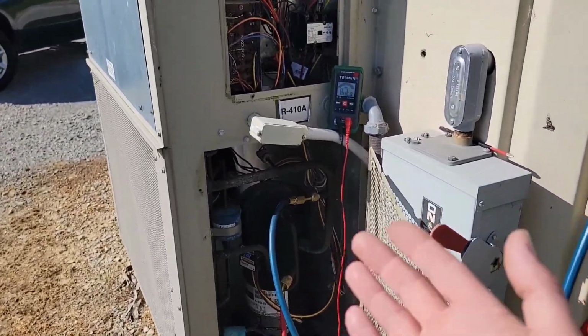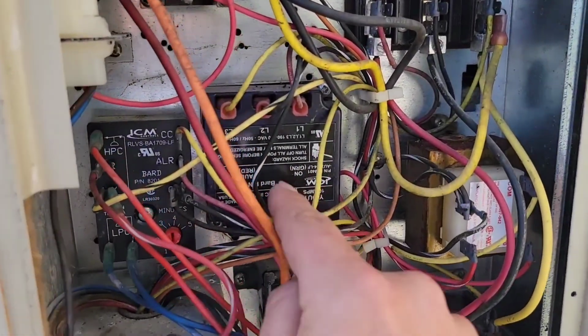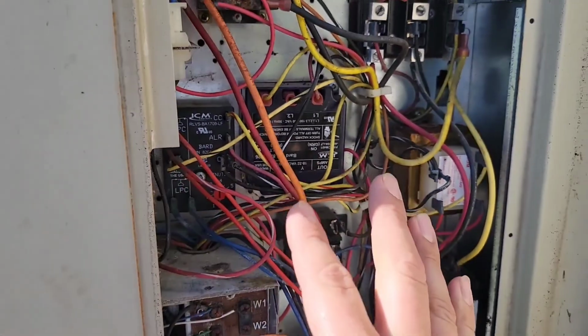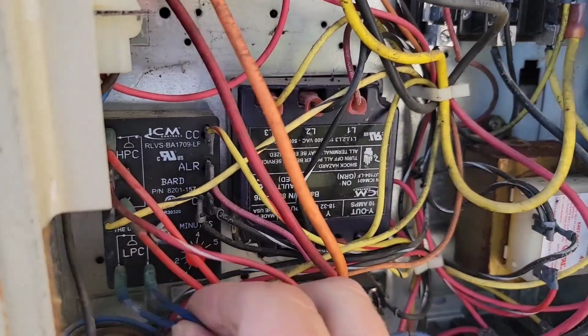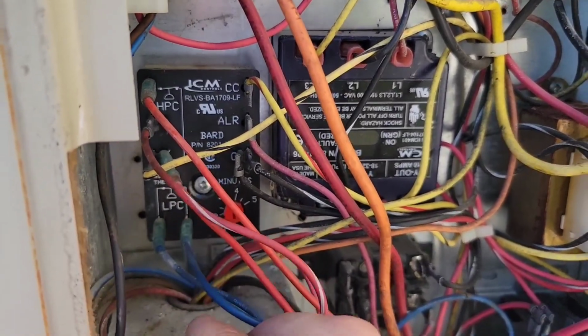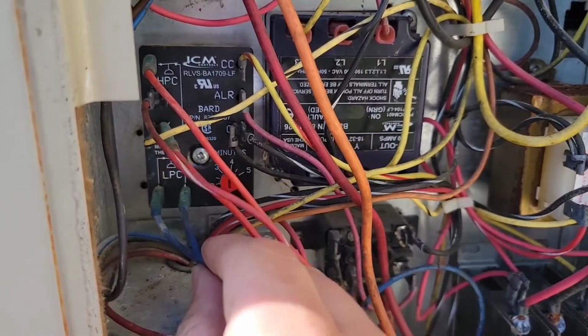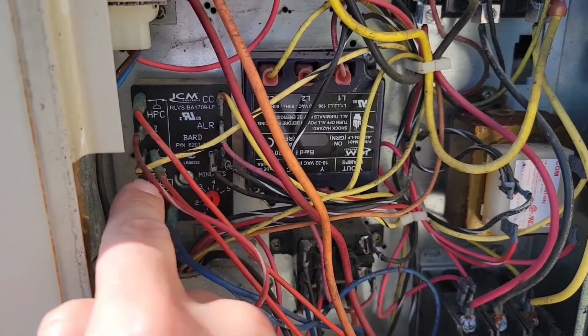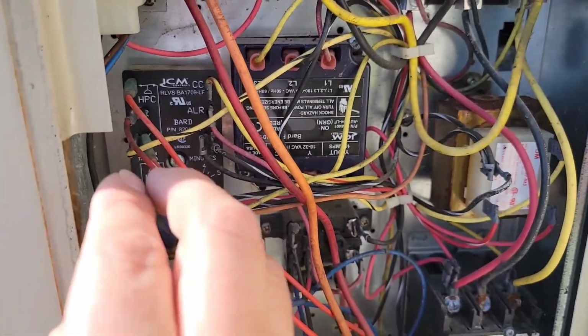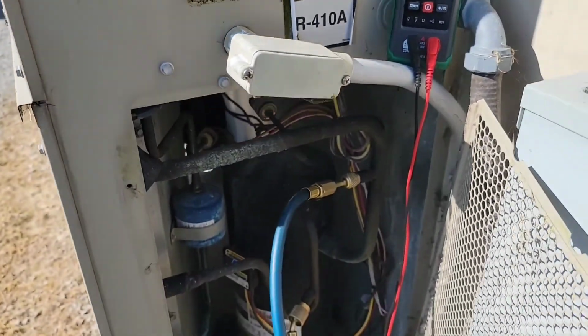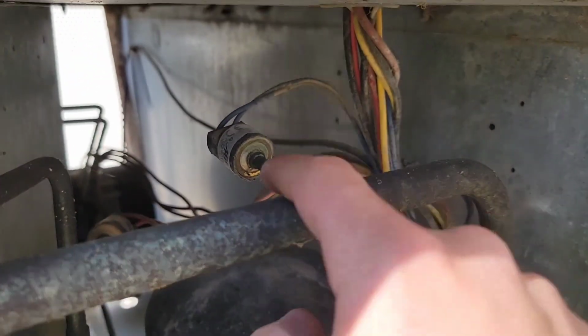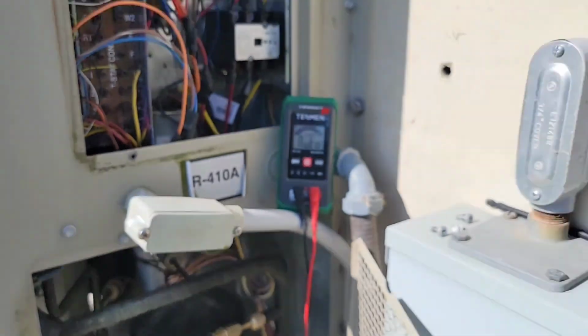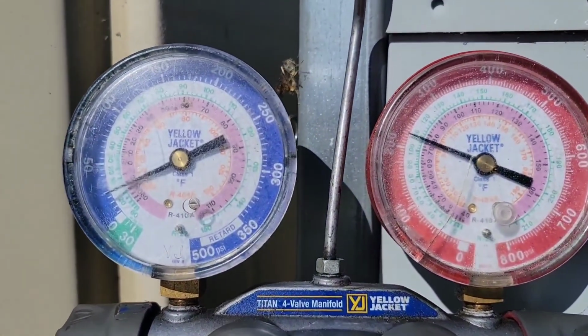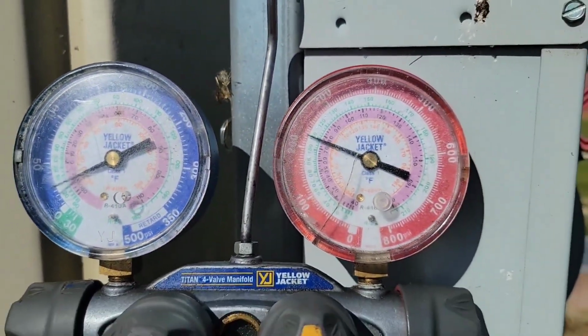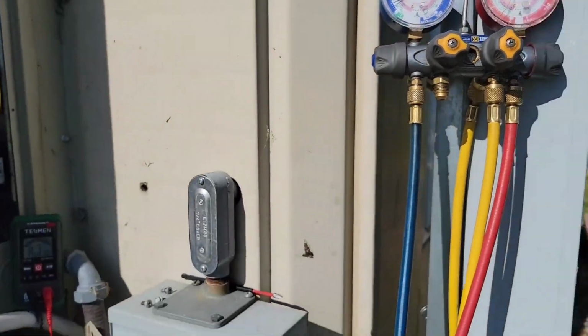So what's happening is we are sensing an alert, an issue, and this module here, this control, is taking the call in, but it's not sending the call out because it's shutting down. Why is it shutting down? Because of this switch. This is a low pressure control, and we have low pressure. So we need to figure out where the leak is. We don't want to just charge the system.